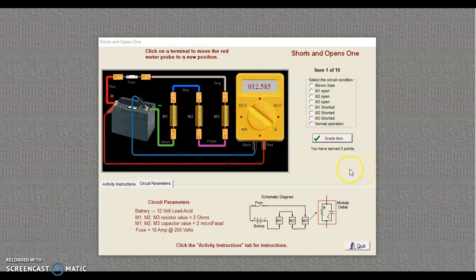So when approaching this problem, let's consider their possibilities. We could have a blown fuse. We could have an open module, one of the modules open, or one of the modules could be shorted. Or we could just be seeing a situation that is a normal operation. Know your source voltage going into this and consider what is between the probes as you probe the circuit.